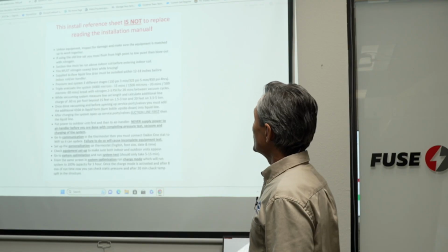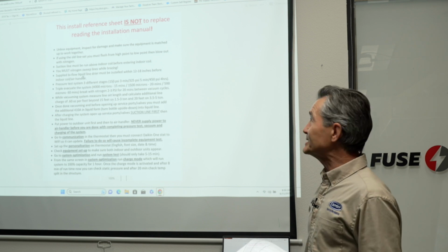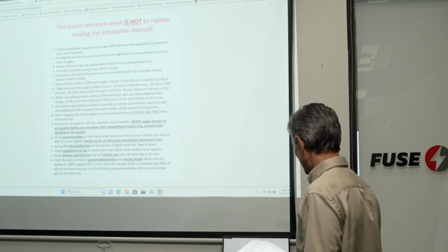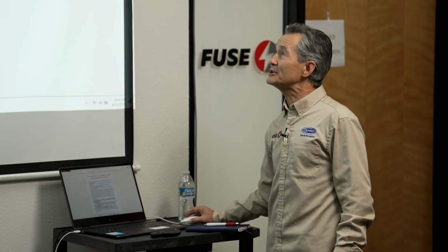Let's go back over here. During the brazing, nitrogen sweep. Firstly, because we are already using, let's say, an old line set, you really have to purge it first with nitrogen, and at the same time, during the brazing, use nitrogen. Mitsubishi required that as well, but in here, Daikin requires the same thing. And it says must. You guys can see this, right? Must means you have to. The equipment you're receiving for the installation will come with a line dryer. It needs to be installed within 12 to 18 inches before the indoor coil or air handler. It allows it to be closer to the outside unit, but the manufacturer recommends doing that. It doesn't say must in here, but it's recommended to put it closer to the air handler.